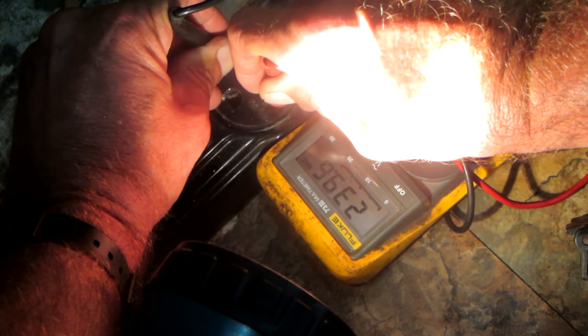Now I go from hot to hot with my meter leads and I should read my 220 volts. And here you see 239. Everything checks good. Remember your safety precautions. Hope you enjoyed this video.